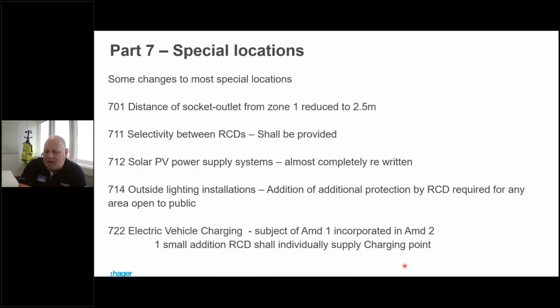Right, part 7. Now we're getting towards the back of the regulations. All right, so there's been some changes to most of the special locations. 701. Now, this is a little change, really. So from the edge of zone 1, we have reduced the distance that we can have a socket from 3 meters down to 2.5. We're slowly falling in line with Europe. Okay, in Europe, if you go on holiday, you'll see that there's usually a socket in a bathroom.